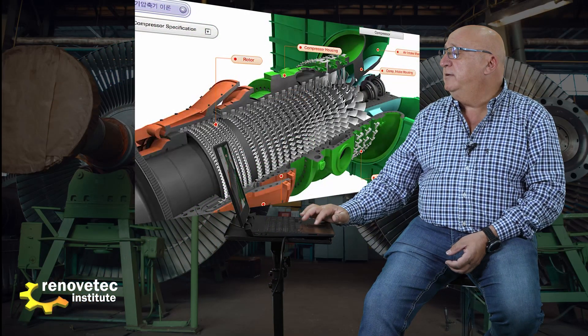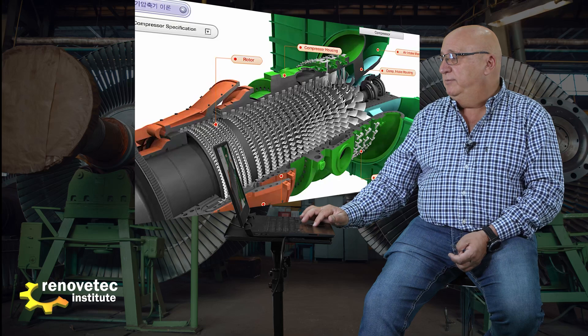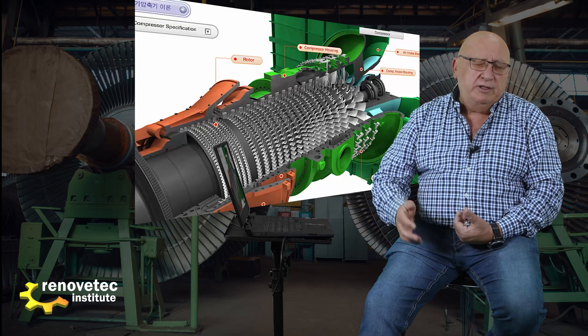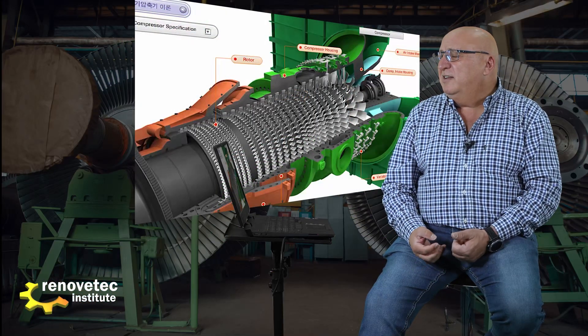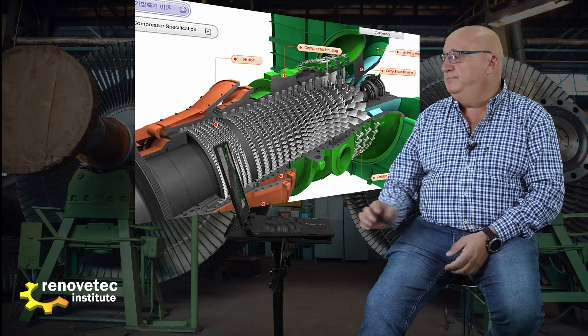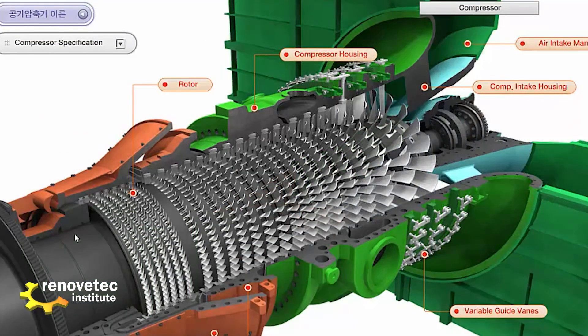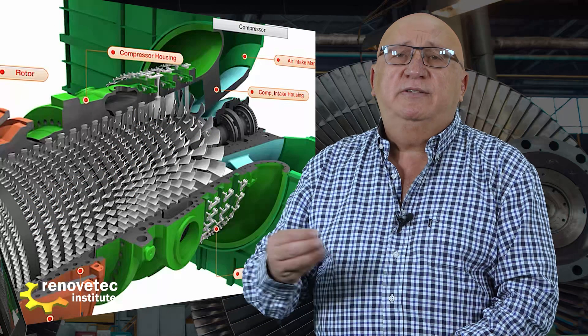In this turbine model, we increase the pressure significantly. While other turbines normally work between 10 and 15 bar at the compressor outlet, this turbine works at a pressure near 30 bar. The inlet is at ambient pressure and the outlet is at 30 bar. At different points, a small amount of air is extracted to refrigerate the combustion chamber and the first stage of the expansion turbine.